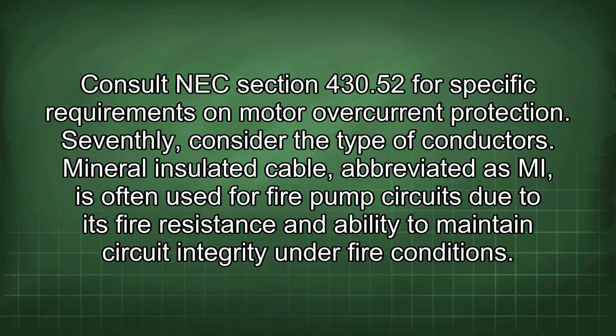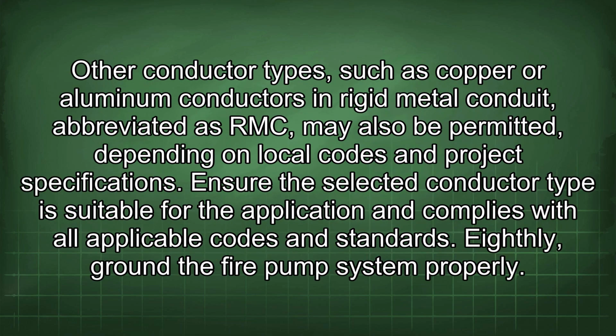Seventhly, consider the type of conductors. Mineral insulated cable, abbreviated as MI, is often used for fire pump circuits due to its fire resistance and ability to maintain circuit integrity under fire conditions. Other conductor types, such as copper or aluminum conductors in rigid metal conduit, abbreviated as RMC, may also be permitted, depending on local codes and project specifications. Ensure the selected conductor type is suitable for the application and complies with all applicable codes and standards.